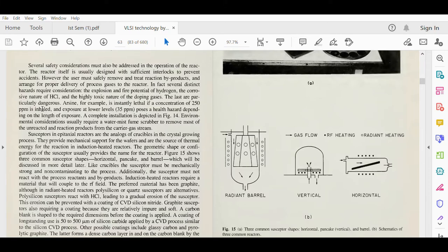If arsine is inhaled in the concentration of 250 ppm, it produces a very hazardous condition. Exposure at lower levels, 35 ppm, poses a health hazard depending on the length of exposure.